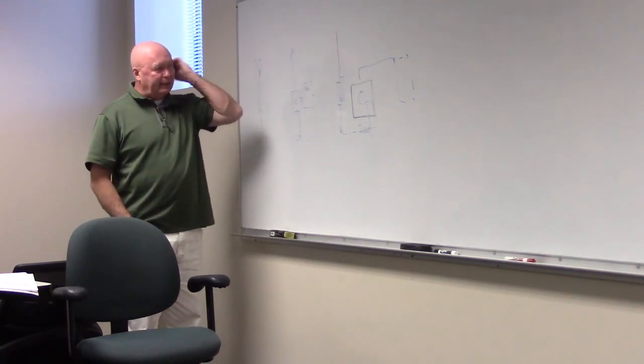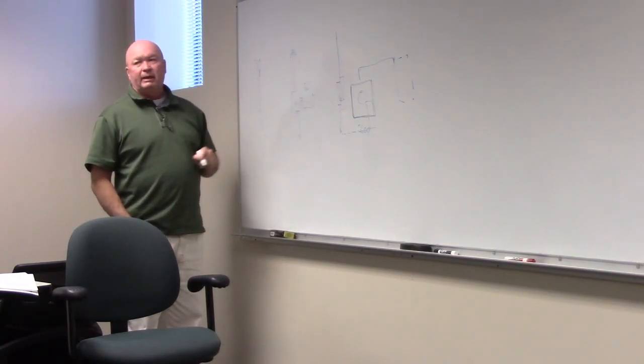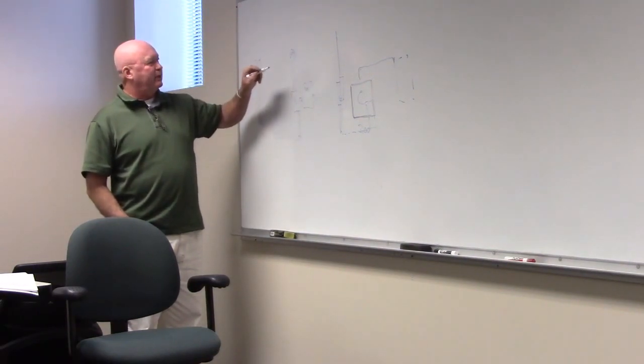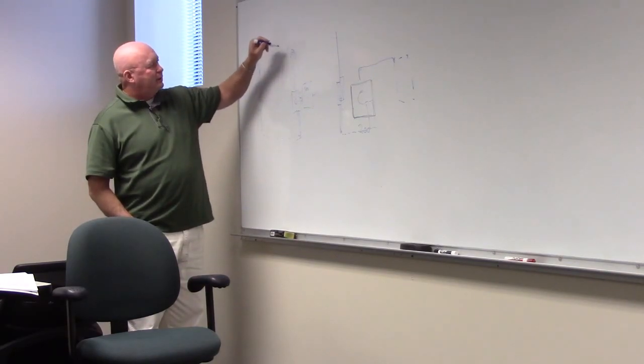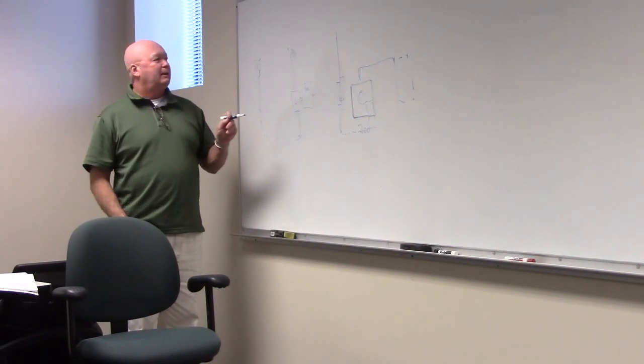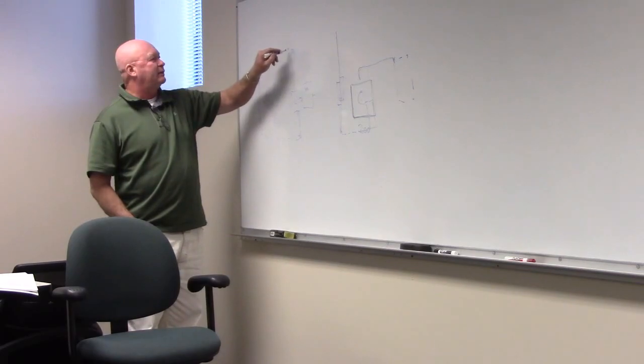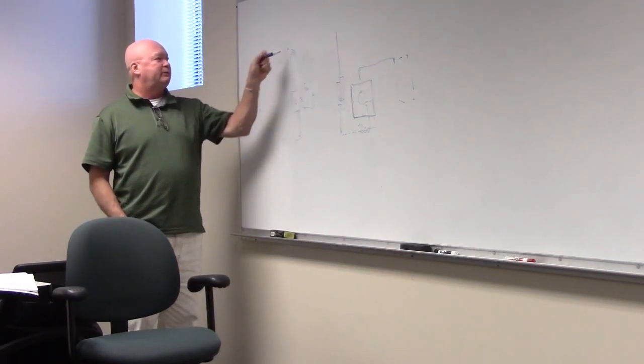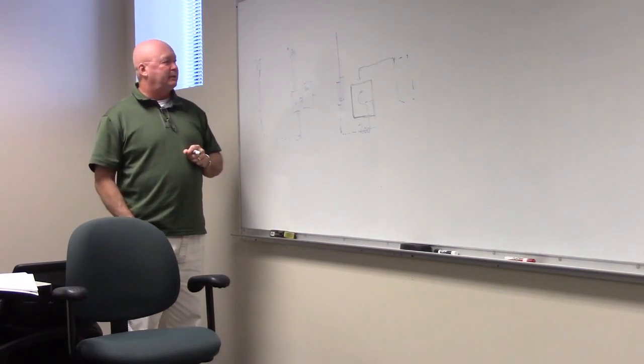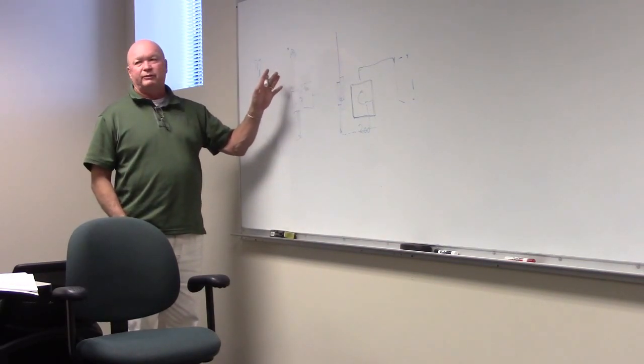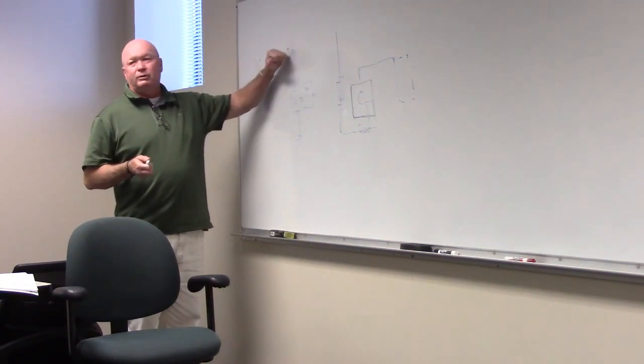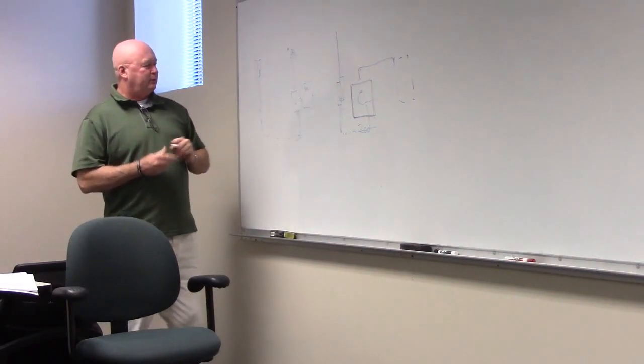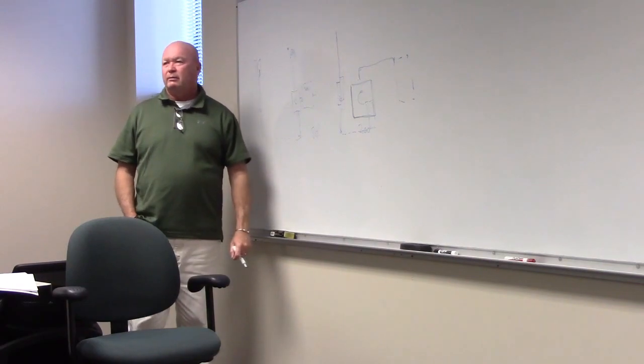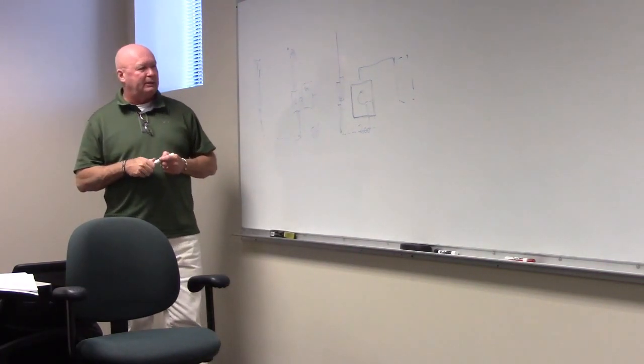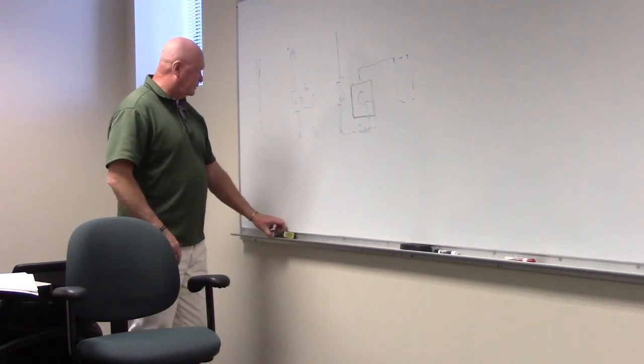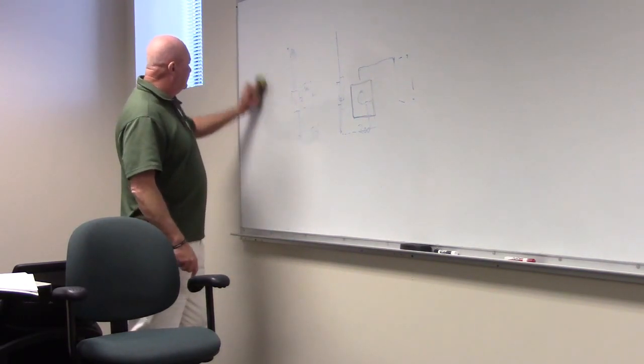So, it just depends, overhead or underground. And again, this is our point of attachment here. We usually just hang the wires out and then they connect to it. Now one of the things you've got to have, especially if you're overhead, you have to give them a service point of attachment. That's usually like a through bolt on the building or on a house, where when they bring in their overhead riser, they have something to attach their wires to and hold it off. That's a requirement. It takes the tension off your service riser by them being able to go over there and clamp to that. Because a lot of times, I think the general rule is they can come up to 80 foot overhead without setting another pole. I think I'm right in saying that. So that's kind of what we're talking about here, service equipment, overhead and underground.